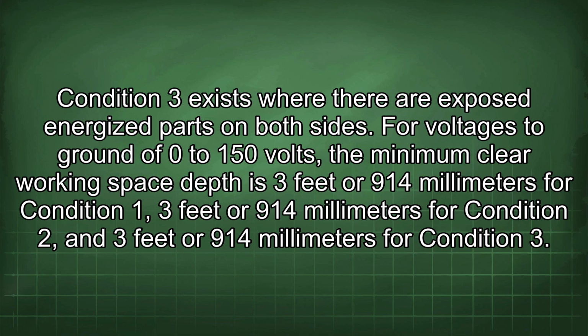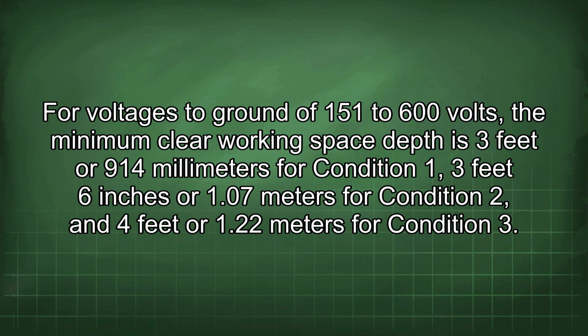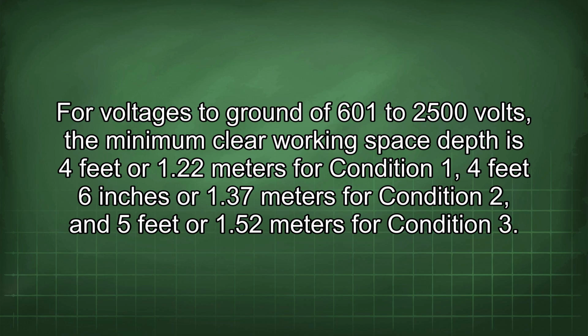For voltages to ground of 0 to 150 volts, the minimum clear working space depth is 3 feet or 914 millimeters for condition 1, 3 feet or 914 millimeters for condition 2, and 3 feet or 914 millimeters for condition 3. For voltages to ground of 151 to 600 volts, the minimum clear working space depth is 3 feet or 914 millimeters for condition 1, 3 feet 6 inches or 1.07 meters for condition 2, and 4 feet or 1.22 meters for condition 3. For voltages to ground of 601 to 2500 volts, the minimum clear working space depth is 4 feet or 1.22 meters for condition 1, 4 feet 6 inches or 1.37 meters for condition 2, and 5 feet or 1.52 meters for condition 3.